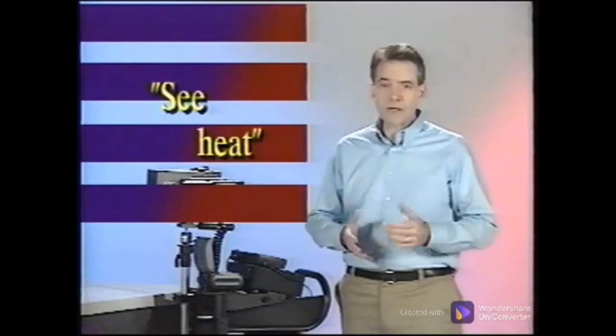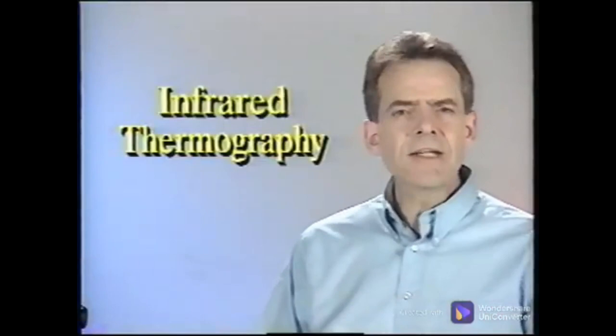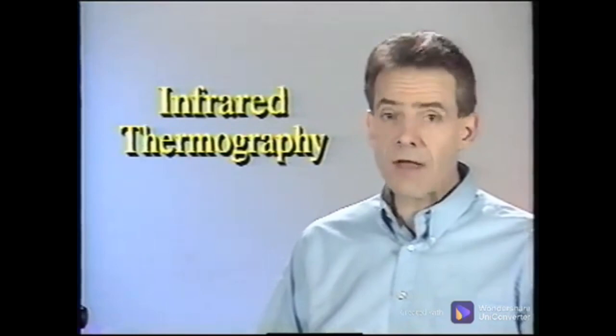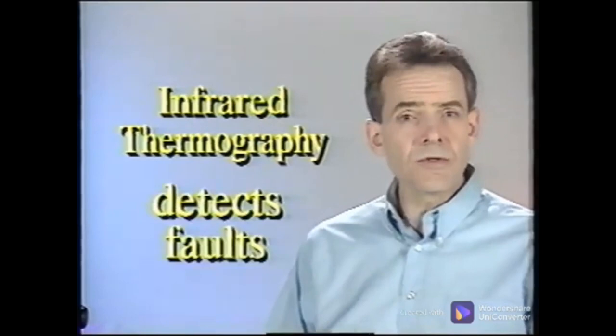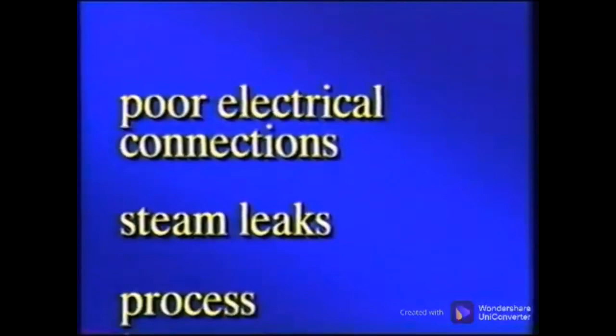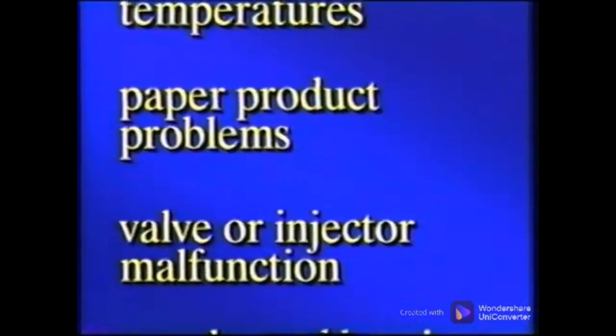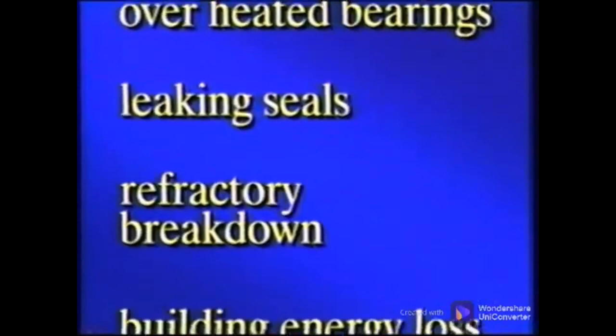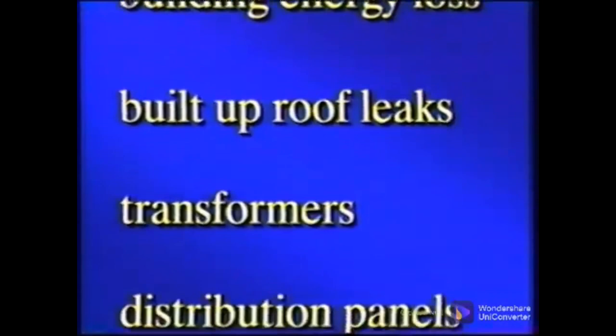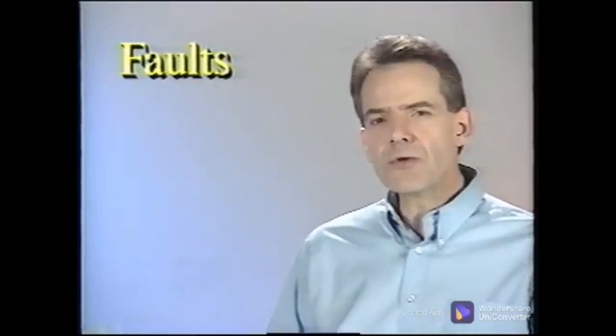Because heat, or the lack of it, can indicate emerging machine and equipment problems, infrared thermography can detect faults that elude other predictive maintenance technologies. It can be used to detect faults such as poor electrical connections and splices, steam leaks, temperature fluctuations in processes, cold spots in paper machine dryer rolls, valve or injector malfunction, overheated bearings, leaking seals, refractory breakdown, building energy and heat loss, built-up roof leaks, and problems in transformers, distribution panels, motor stators and rotors, as well as determining levels in tanks. In the field of thermography, a fault is usually referred to as an anomaly or nonconformity.